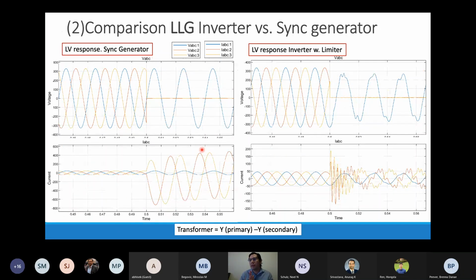So here I'm testing the same case of study, but for a line-to-line ground fault. And again, the fault happens at 0.5 seconds. We have on the left-hand side the test system with the synchronous generator. On the right-hand side, we have our inverter model with limiters implemented. And again, we have some small jittering, correct? But after less than a cycle, we get the trimmed version, which is what we are expecting, based on the parameters we defined to prevent, again, as I said, further damage to the inverter.